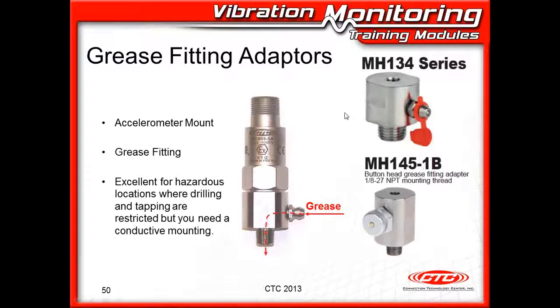We also make grease fitting adapters, so you can remove the existing grease fittings in the machines. You can install the adapter. You still get to grease the machine through the 90-degree grease fitting. The biggest application we see for these is in hazardous areas. A lot of the requirements for hazardous areas say you have to have a conductive mechanical mount, so that eliminates any epoxy. It eliminates any magnets. These are very easy because you can remove those existing grease fittings. You also run into manufacturers of explosion-proof motors and things that say if you penetrate the motor, you may void the warranty. This is a way to get that connection without any issues. So look for these. They come in both the standard grease fitting and the button head.